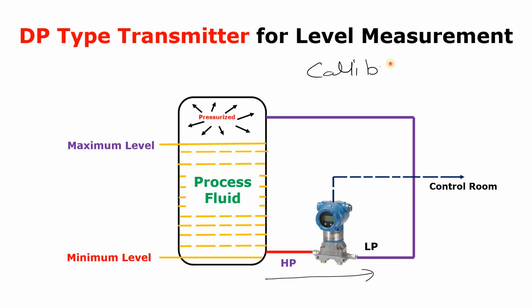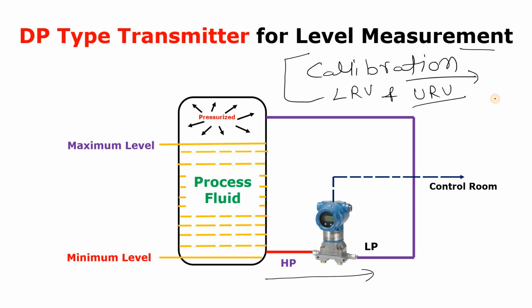For calibration, we use mainly two parameters. The first one is LRV, that is the low range value, and the second is URV, that is the upper range value. On the basis of these two parameters, LRV and URV, we calibrate our transmitter. That's why we show the level in the control room. In the next video we will discuss how we calibrate the transmitter and how it shows the reading. We will discuss how we take the range of the LRV and URV. It mainly depends on the height of our tank, and on the maximum level and minimum level. We will discuss that in our next video.